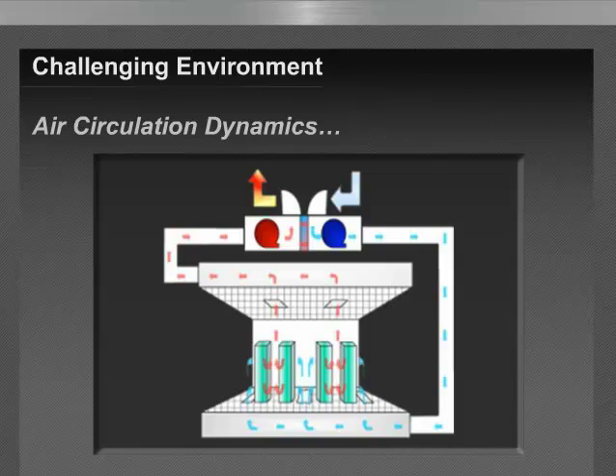So if we look at it from that respect, what we're doing is we're taking any fire incident and we're taking that smoke and bringing it right out to the environment or to the atmosphere. We're not getting the recirculation. We're not getting the homogeneous mixing of the smoke in the space. And what happens is we have a highly diluted sample of smoke not making it to the ceiling, going directly to exhaust ducts, and never having the opportunity to be detected. And that's the risk in terms of what economization has in terms of performance of smoke detectors, or the expectation that smoke detectors would respond in those various conditions. So with that, we have to consider those as part of the challenge.